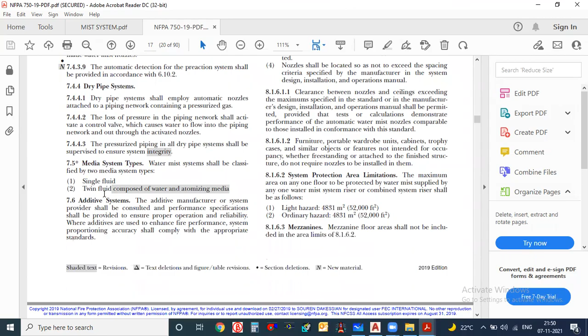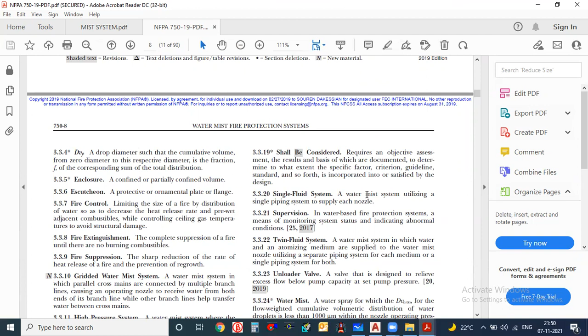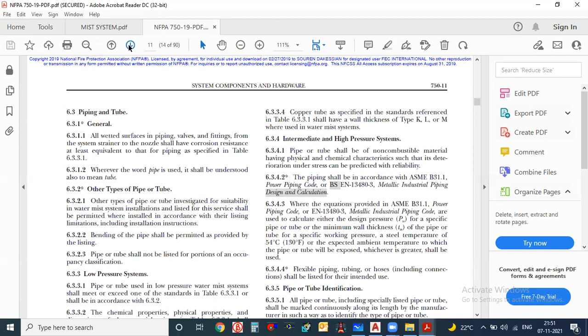So just go a little bit up. Some definition was given here. A water mist system utilizing a single piping system to supply each nozzle is called single fluid. A water mist system in which water and an atomizing medium are supplied to the water mist. Now here they have used one term called atomizing medium. Maybe this atomizing medium is the one which is blocking the radiant heat. Like in a mist system, the heat will be blocked. So maybe because of this atomizing medium, the radiant heat will be blocked and it will be entrapped in that confined space. So that's why they have given the atomizing medium here.